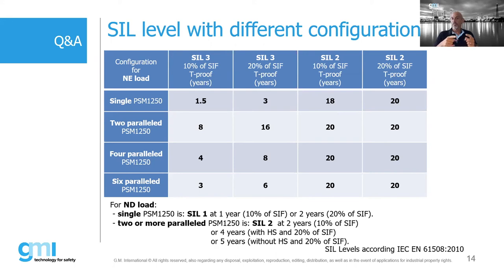If this device is participating with 20% of the SIF, my proof test interval will be extended to 3 years. If I'm using the same power supplies for a SIL2 application, and SIL2 is enough, the testing time will be extended to 18 years. So it will be very long. I can use it for a very long time without testing. That is also important for the end user. If I use it for 20% of the SIF for a SIL2 application, I can have a proof test interval limited to 20 years, which is the lifetime of the power supply.